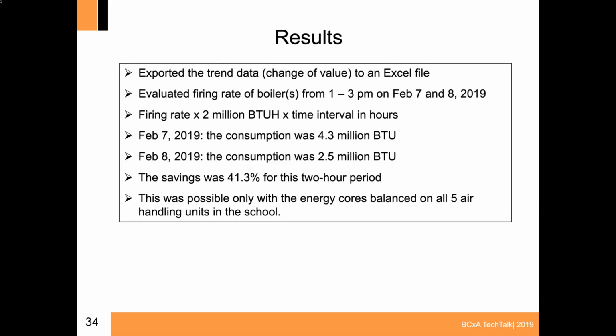So what did we get with our results? When we exported the trend data to the Excel file, we were able to look at the firing rate of the boilers from between 1 to 3 p.m. on February 7th. That was the baseline, and then the same time frame on the 8th. The trends basically showed only when there was a change of value in the firing rates. So we were able to take that firing rate times the boiler capacity. If there was 1 boiler, then it's that, and if it's 2 boilers, then it's the product of the 2 of them, times the time interval that they were at that stage.